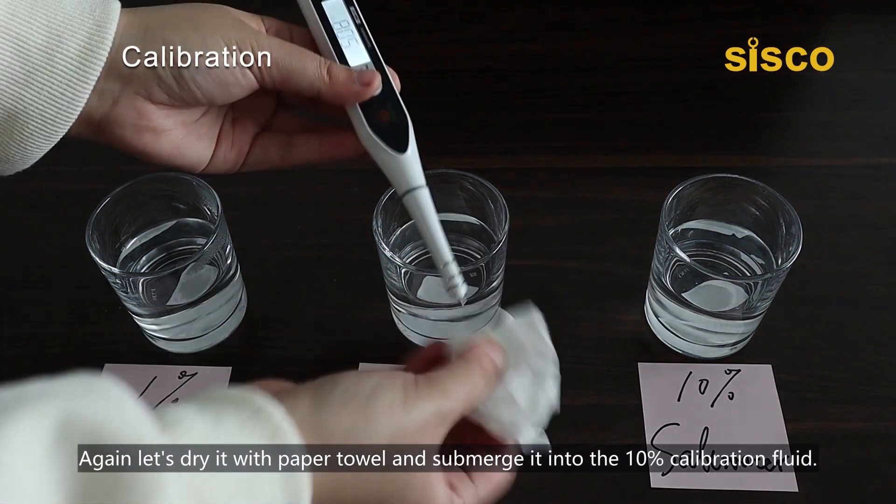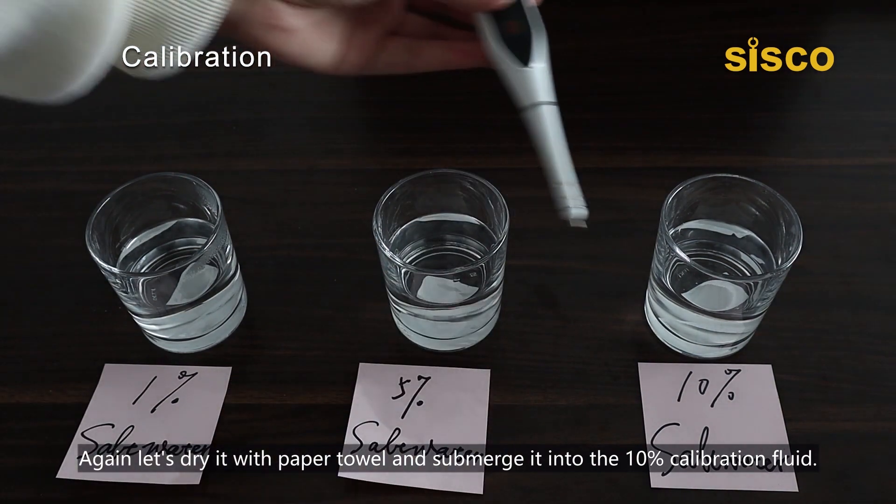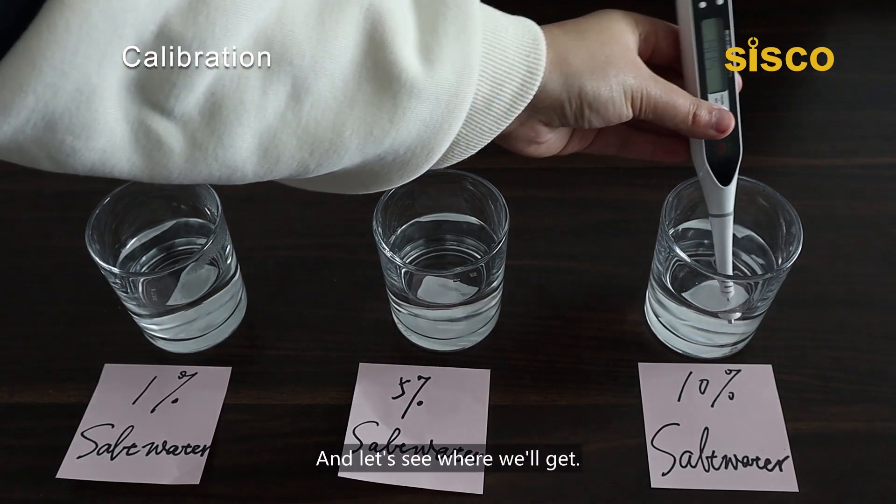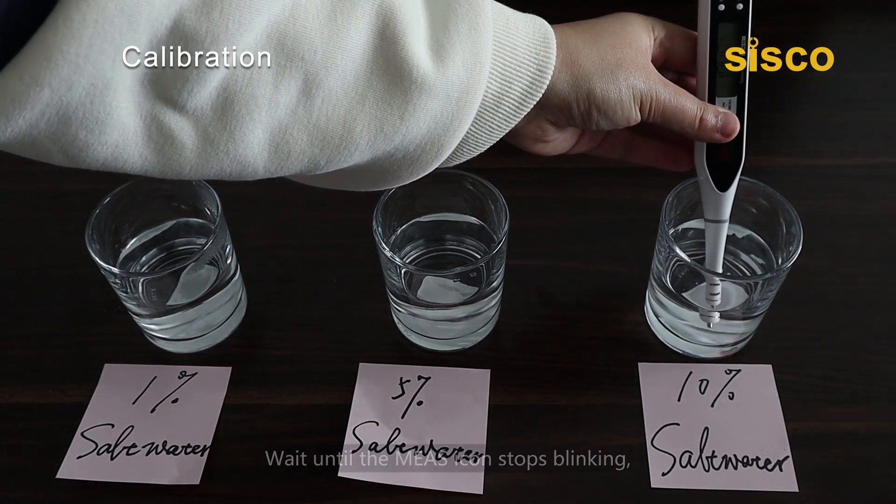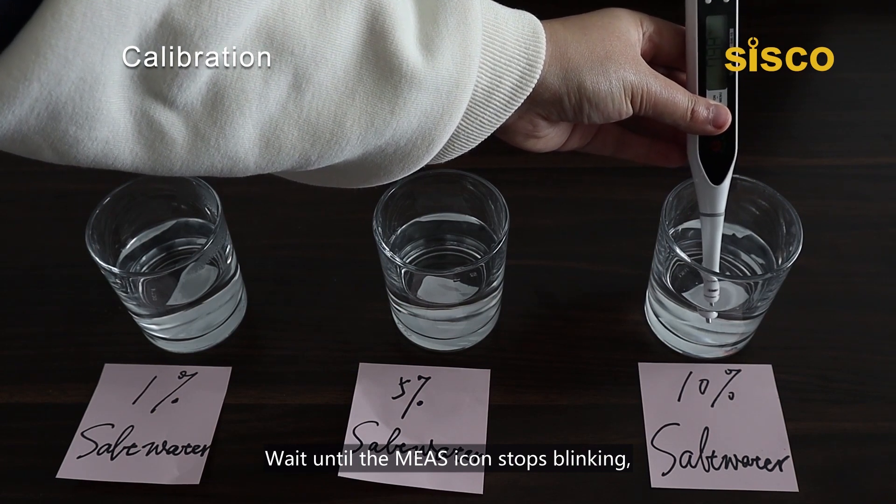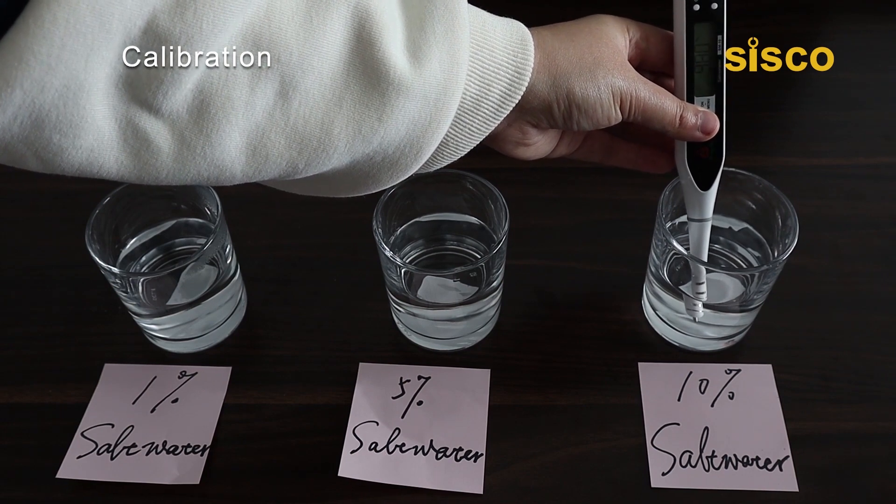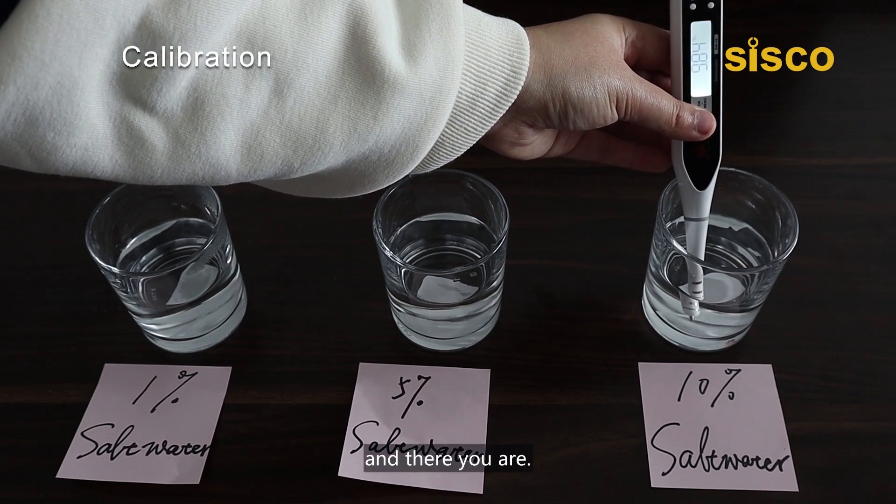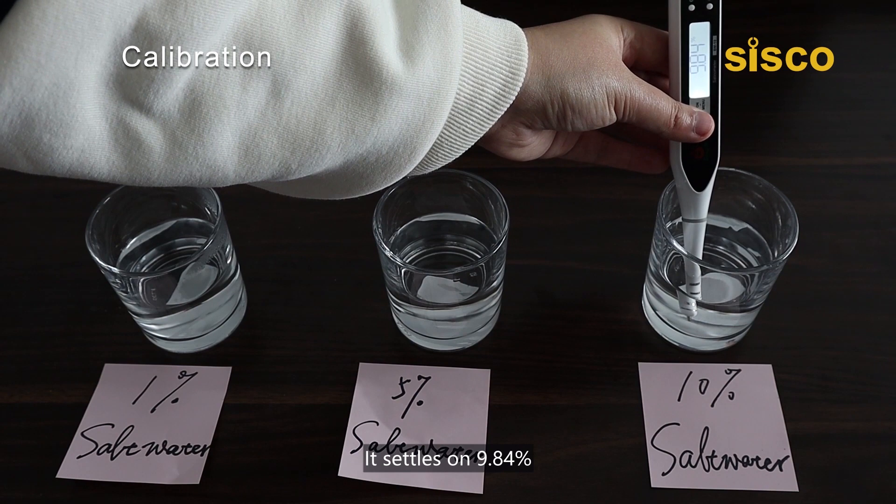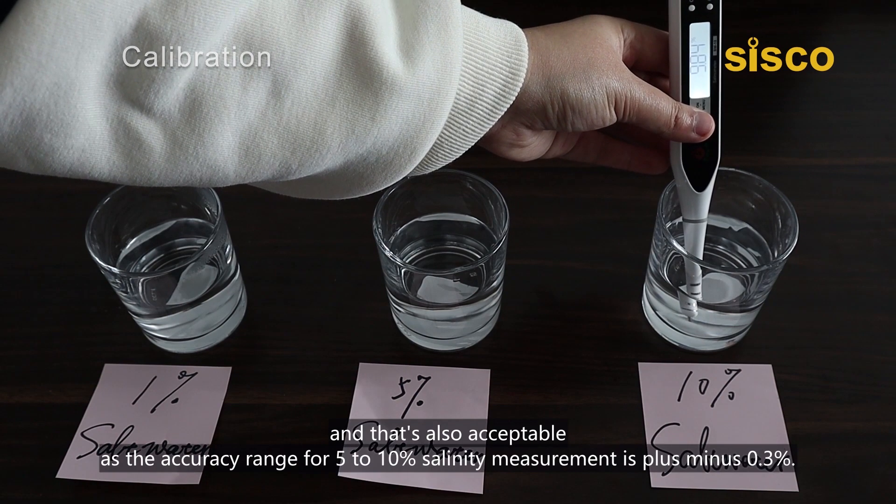Again, let's wipe it with paper towel and submerge it into the 10% calibration fluid, and let's see what we'll get. Wait until the MEAS icon stops blinking. And there you are. It settles on 9.84%, and that's also acceptable, as the accuracy range for 5-10% salinity measurement is ±0.3%.